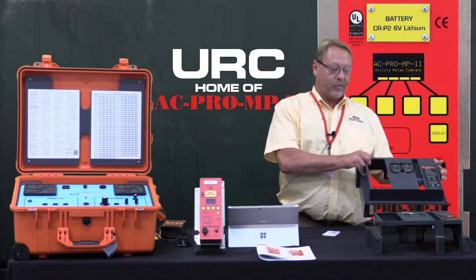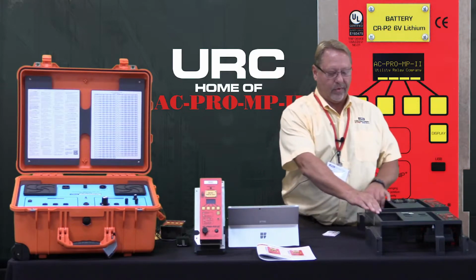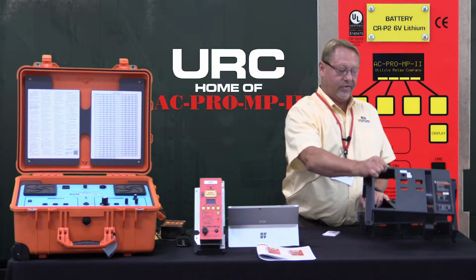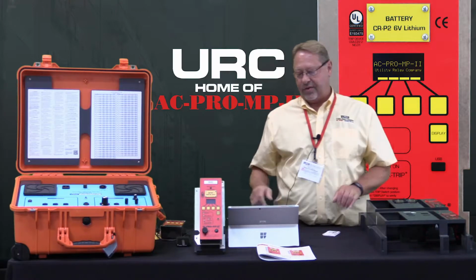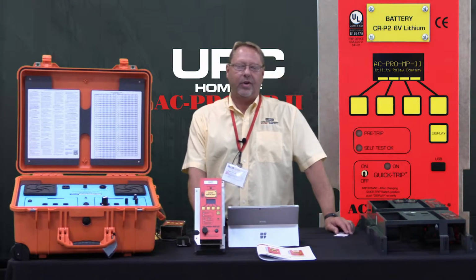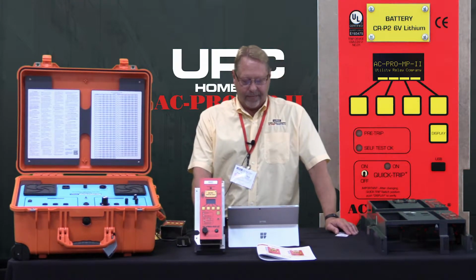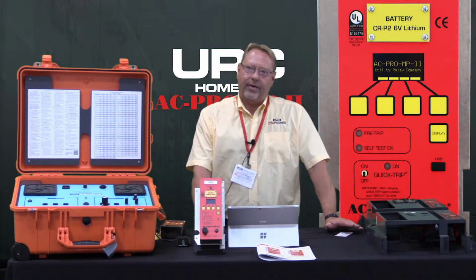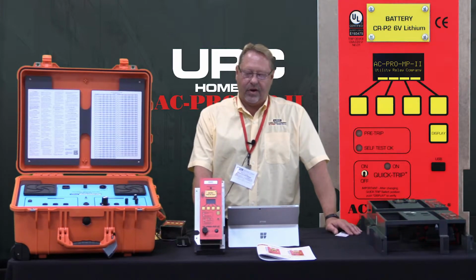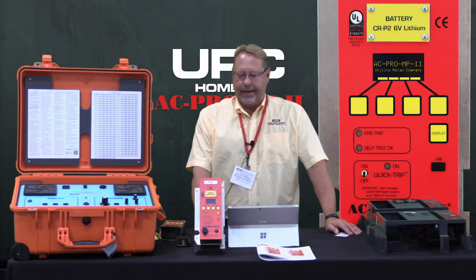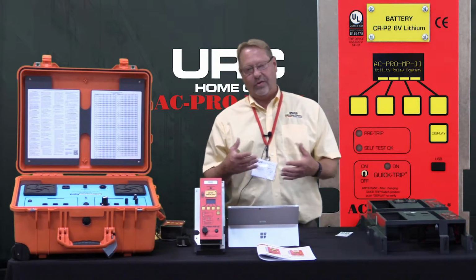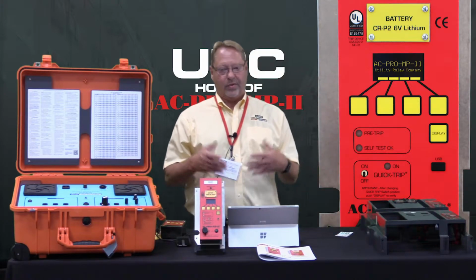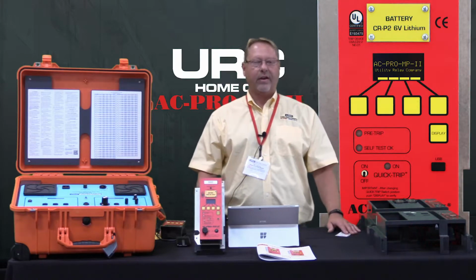Here's a cover from the Square D one. Marketed by Masterpact out of France. Here's that cover for that one. It was also relabeled by a company called Moeller out of Germany. There's a well-known issue with the STR family of trip units, and basically the unit would nuisance trip, and the breaker would open up and cause a lot of customer issues.